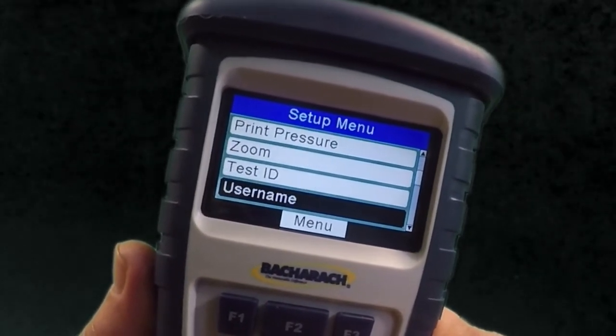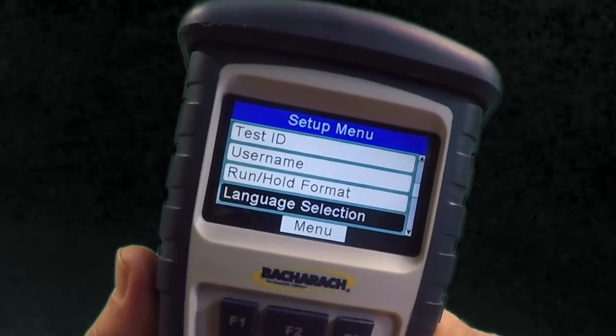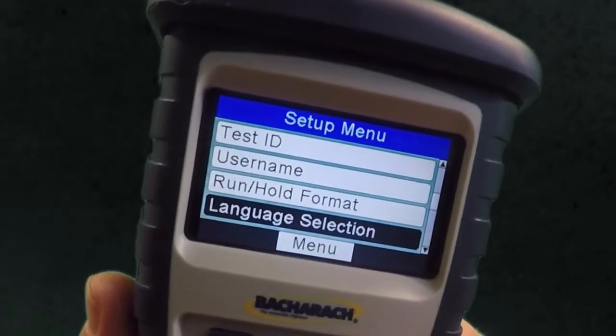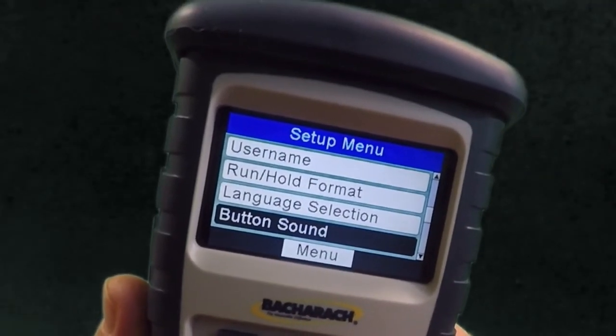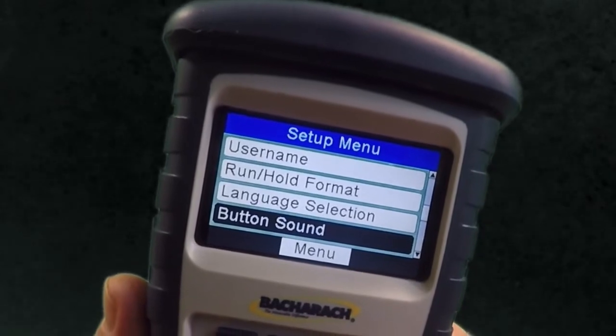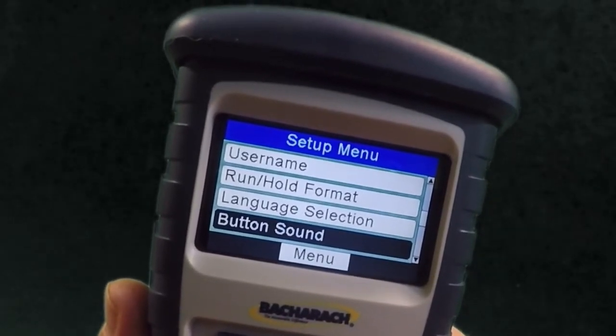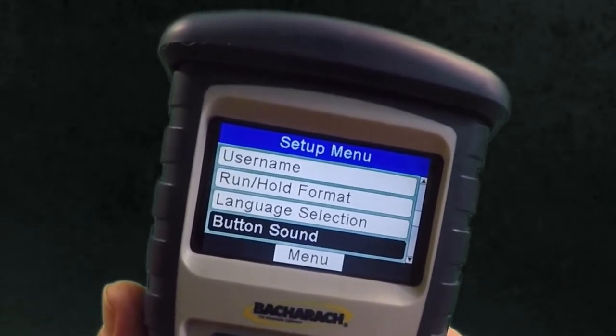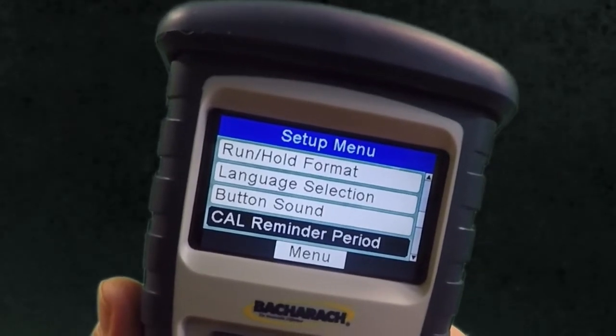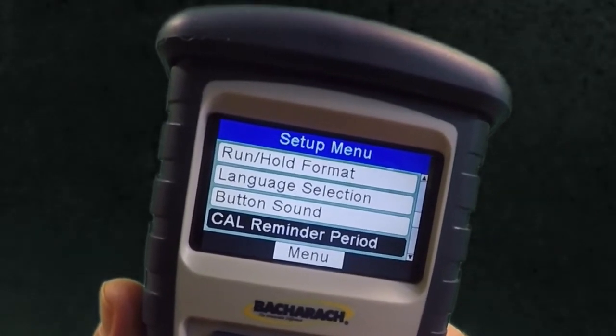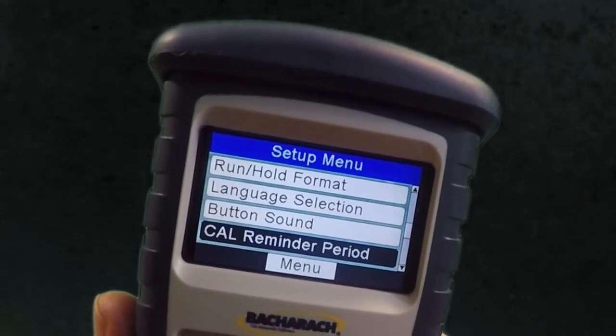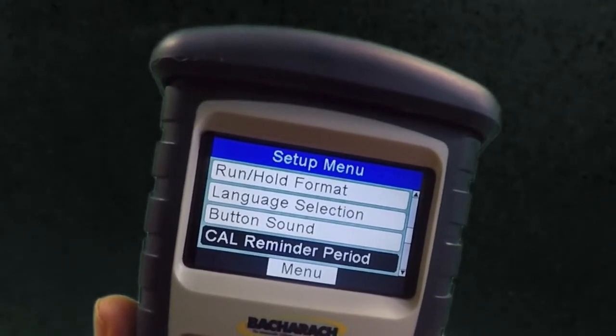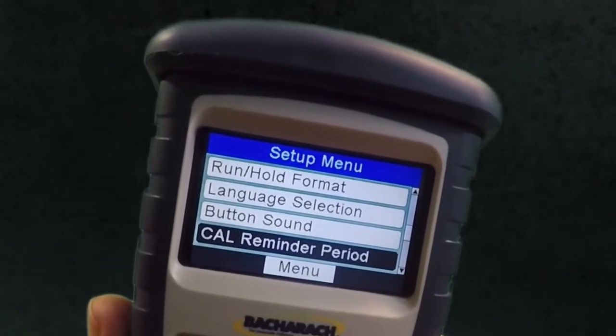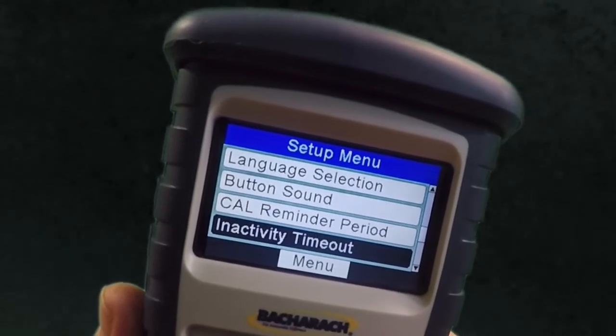We will scroll down to language selection. That's pretty self-explanatory. Button sound, I'm not a big fan of the beeping going on, so I've got it silenced. You can either activate the button sound or not. Cal reminder period gives you a reminder in the display after the 60-second warm-up that the CO sensor needs to be calibrated, and again, I recommend generally once a year.